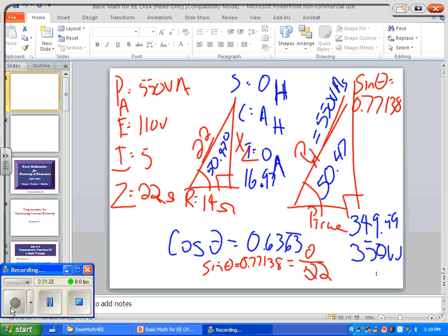And in the future, someday, one of the things you're going to want to be able to do is find out how to get rid of that X sub L. And how much of it do you want to get rid of? Not all of it, but at least 95% of it, because overshooting is worse than being a little short. We want to get close to a 0 degree angle, perfectly efficient, but better to be a little short than blasting past. So generally speaking, we'll take 95% of that and try and fix that circuit. But that's, as I said, for another day. Okay, so that's one of the purposes.